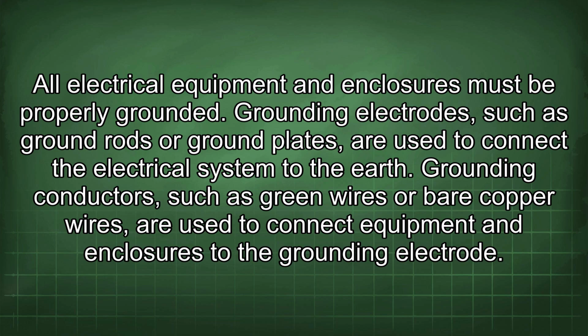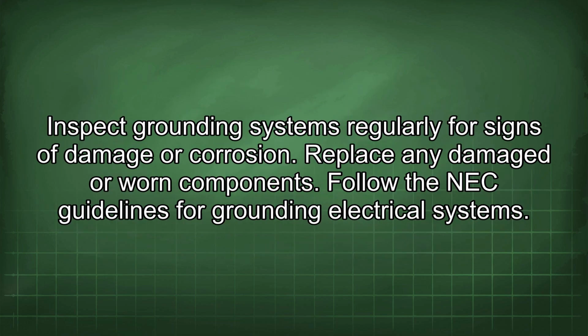Grounding conductors, such as green wires or bare copper wires, are used to connect equipment and enclosures to the grounding electrode. Inspect grounding systems regularly for signs of damage or corrosion. Replace any damaged or worn components. Follow the NEC guidelines for grounding electrical systems.